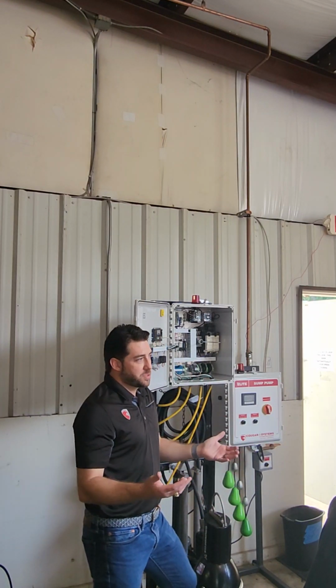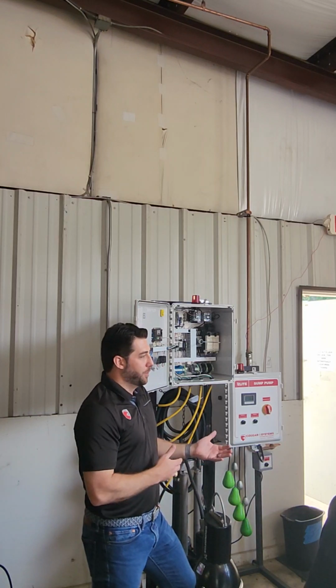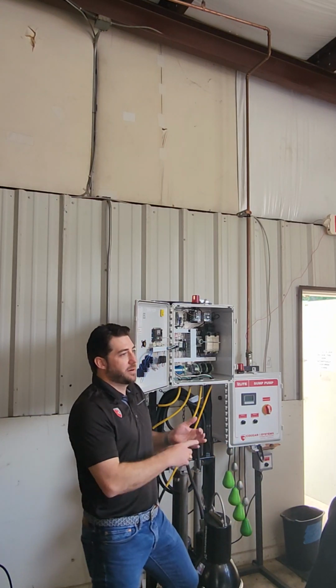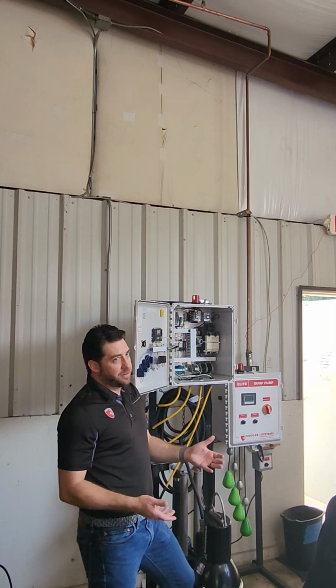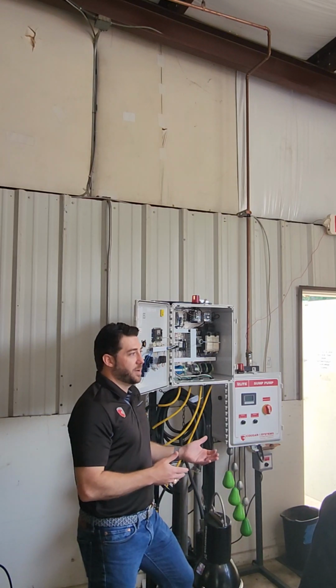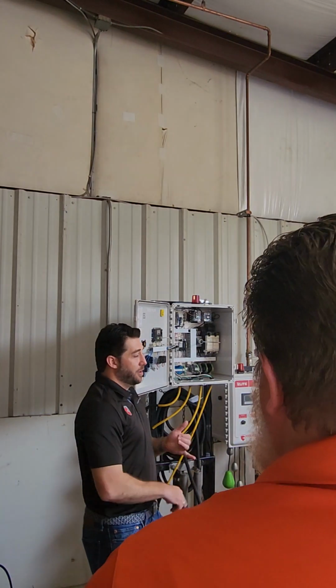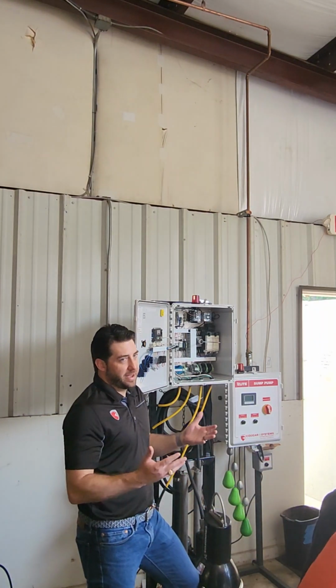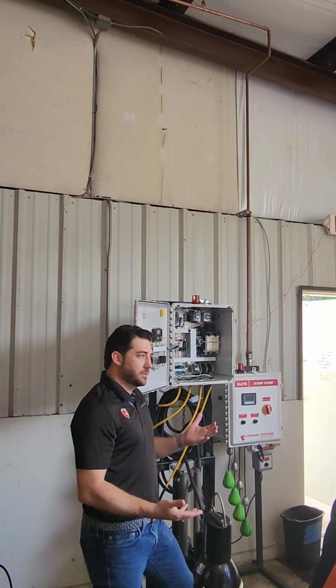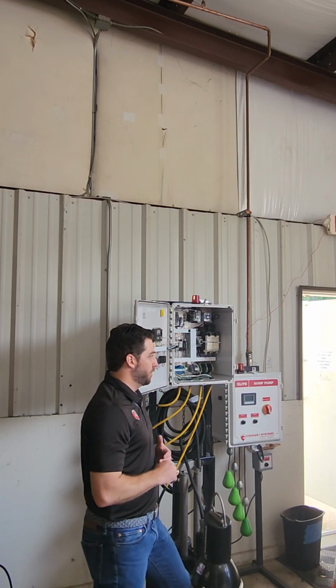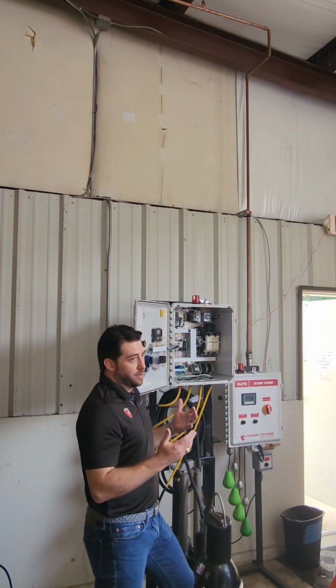And so that's where it's kind of a judgment call. Is it worth it to pull the pump, get it tested, get it repaired, and put it back, or do you let it run to failure and then just replace it anyways? Because now you're going to have a new pump with a new warranty, all of that. Especially on the smaller pumps, it's a judgment call, and it may not be worth doing all that for a seal fail.